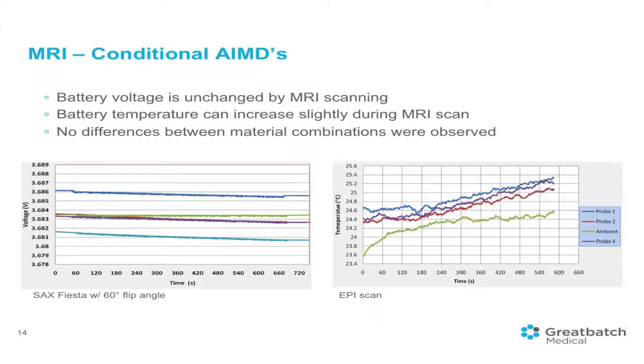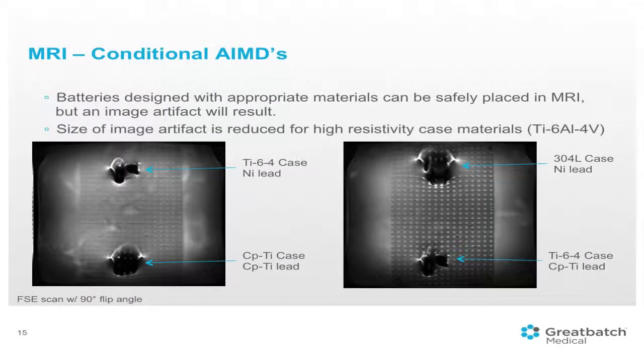So again, this was all, I think, pretty benign. The one thing that certainly putting a battery in an MRI will do is give you an image artifact. There's no doubt about that. And so you can see we had a significant image artifact in all the different combinations of materials we tested. The size of the image artifact was a little bit different depending on the material. If you put this highly resistive titanium 6.4 grade in, you did get a smaller artifact than if you use the commercially pure titanium. And the 304L was actually the worst. And the nickel lead really didn't make much difference at all.